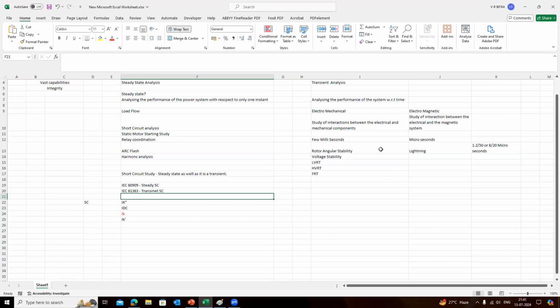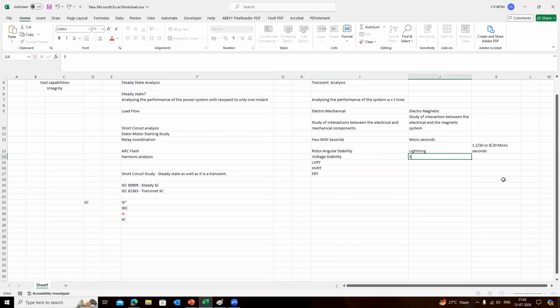What is the transient analysis? As I mentioned, the transient analysis is analyzing the performance of the system with respect to time, and it has been classified into two categories: electromechanical or RMS transients and electromagnetic transients. Under the RMS category, there are further studies like rotor angular stability, voltage stability, LVRT, HVRT, etc.